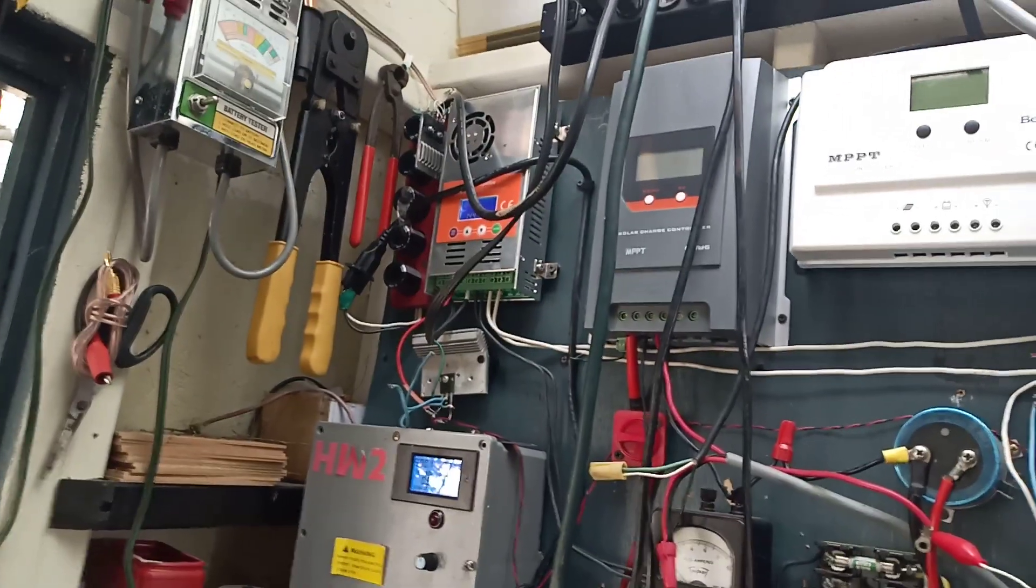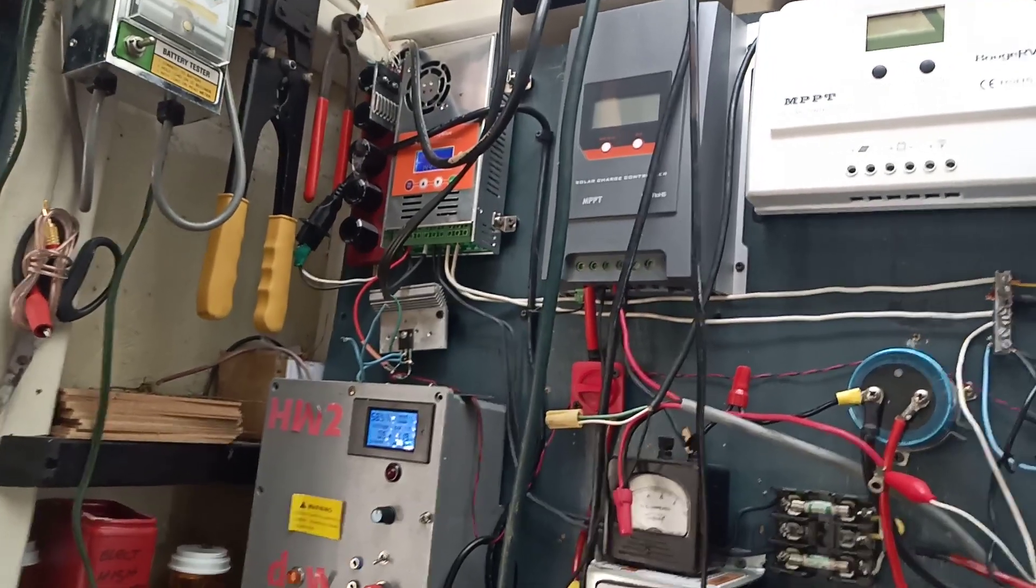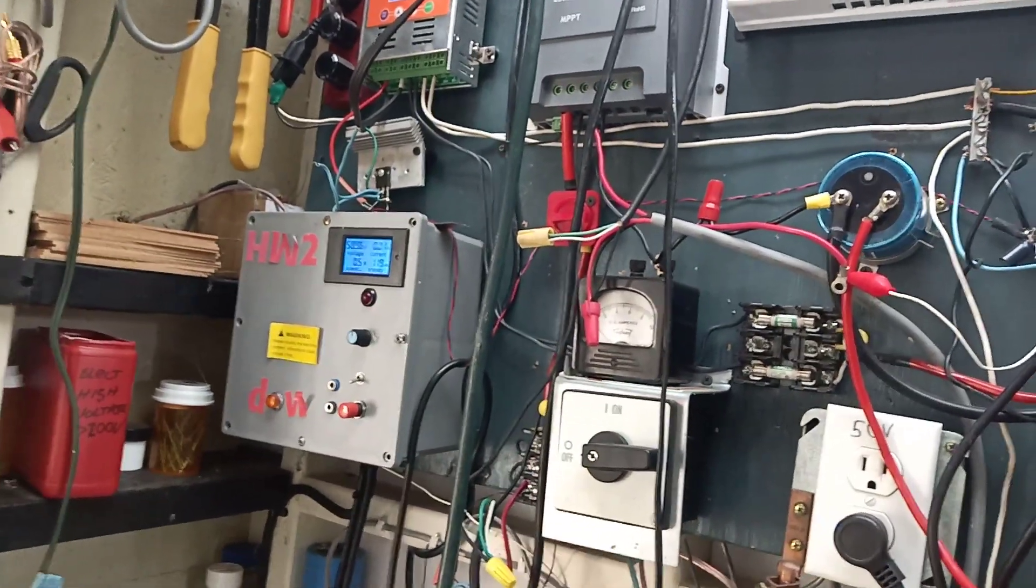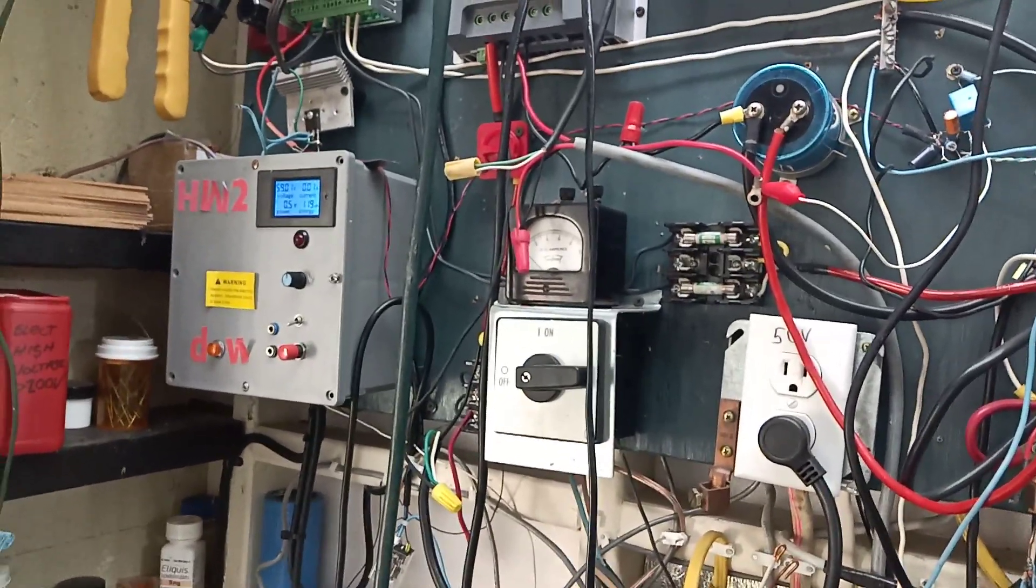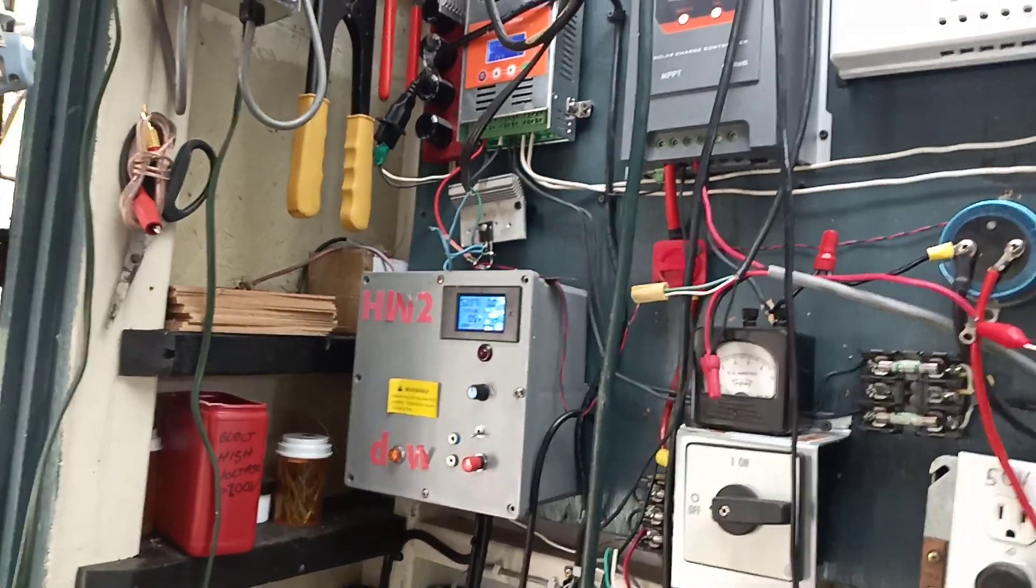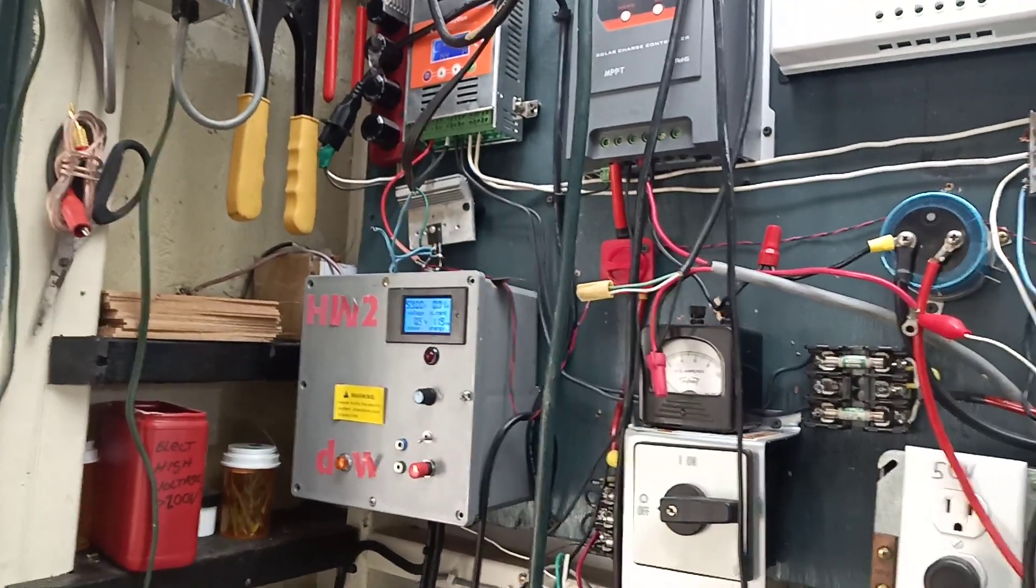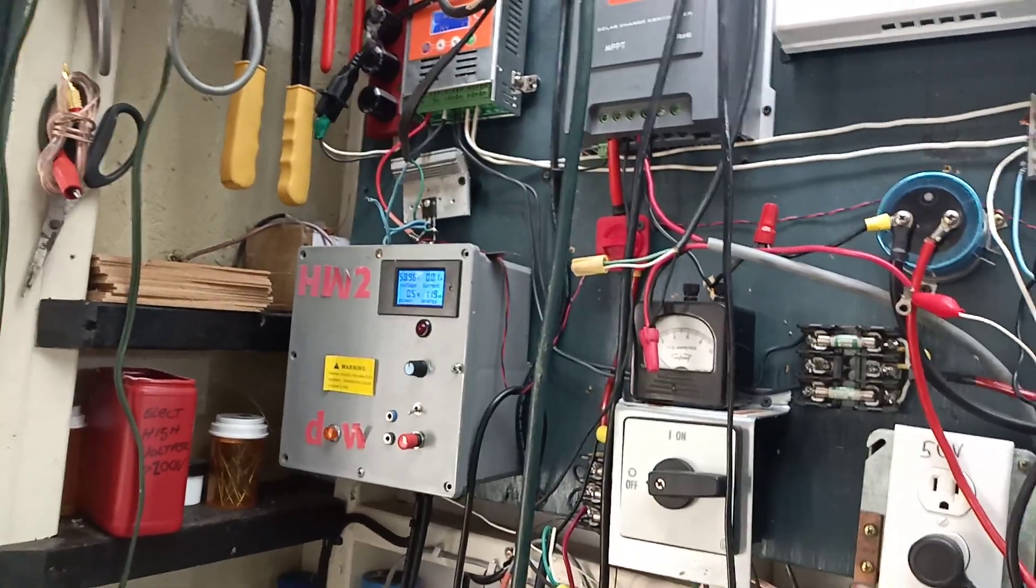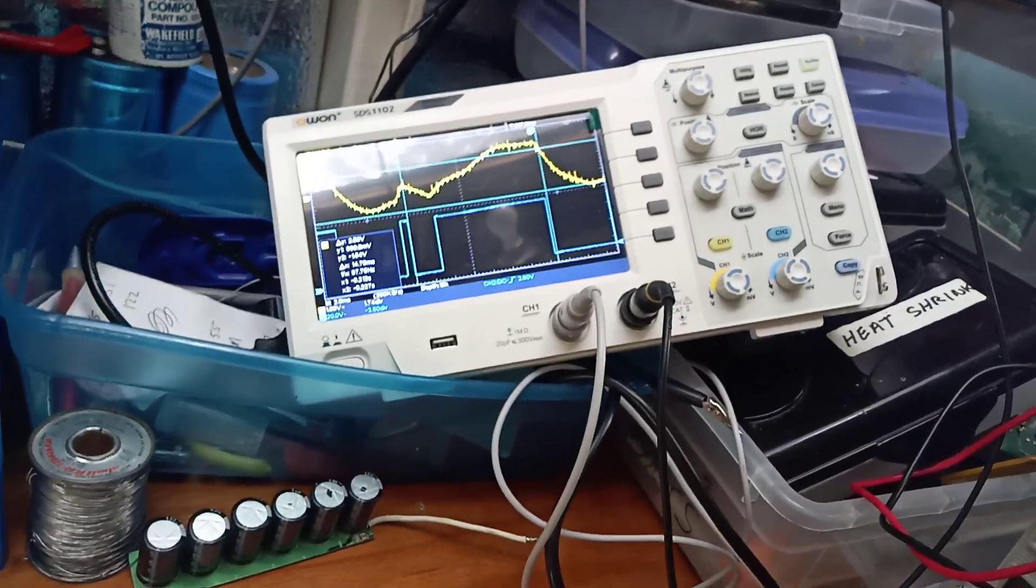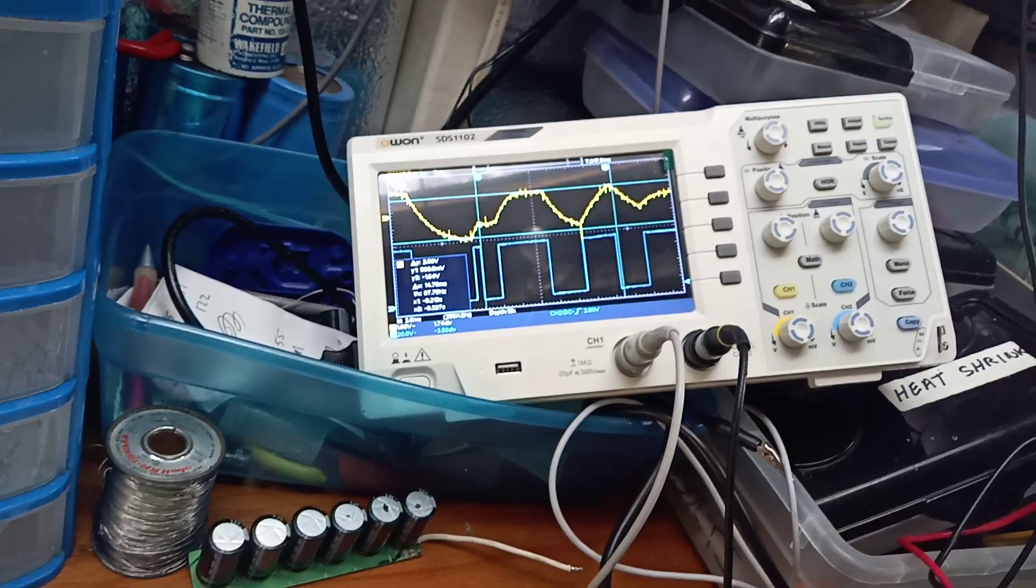When the charge controller is not actually drawing enough power, if your batteries are full, you're not running some refrigerator or something like that, the power point voltage is exceeded. This is a 60 volt array, some of the panels are 58, some are 60, but when it gets hot, like today when you get a little sun on, your actual real power point is like 57 volts. When you are not drawing current through a charge controller charging your battery, the array voltage goes up. When it goes up, when it's over what you expect the power point voltage to be, that voltage and power can be diverted into heating water.